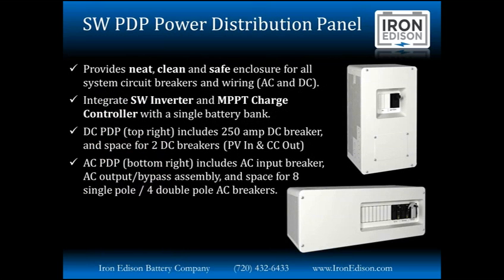Next, we're going to get into the power distribution panels that are available from Schneider. First one, this one is compatible with the SW inverter line. It provides a very neat, clean, and safe enclosure for all the system circuit breakers and wiring, both on the AC side and the DC side. With the SW PDP, you can incorporate one or two SW inverters, as well as an MPPT charge controller, either the 60 amp or the 80 amp, and a single battery bank.